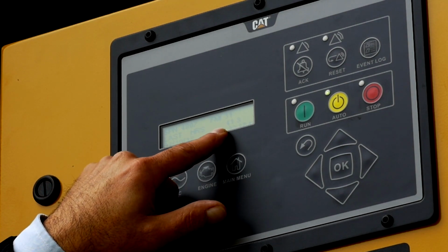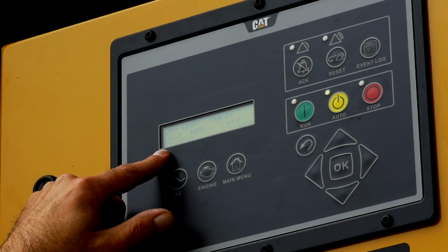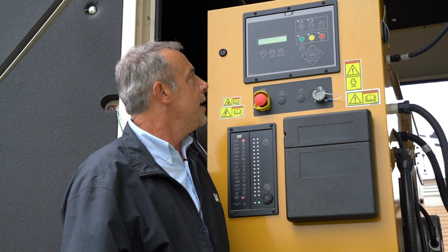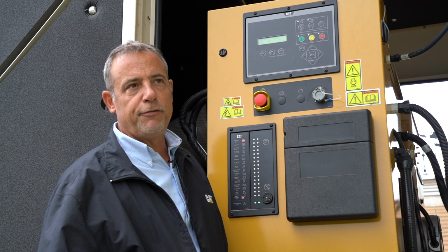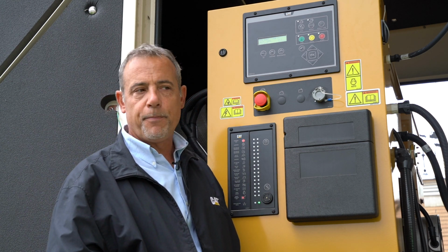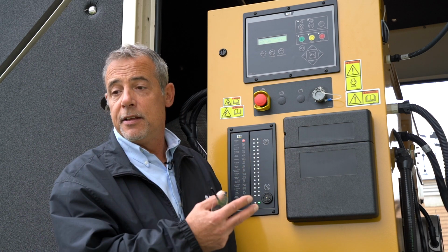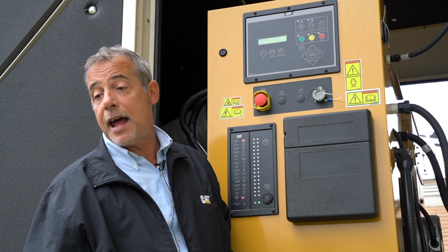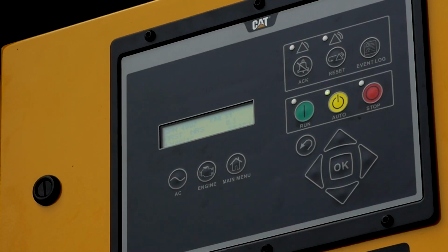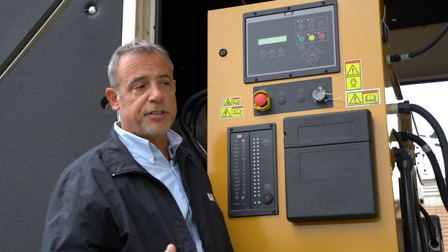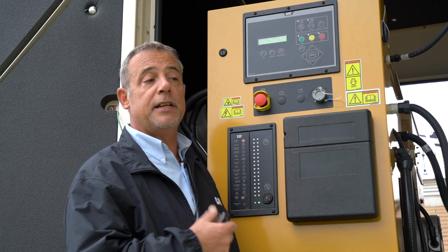The last time it happened was at 41 hours, the 23rd of October at 22:37. And that's a good thing if you have a fault where you come in from the weekend and you think somebody might have been screwing around, they hit the e-stop, you could always go back and see when that happened. And that does that for every fault. And it gives you the first time it happened and the last time. So you could actually see the first time it ever happened on the machine and the last time.